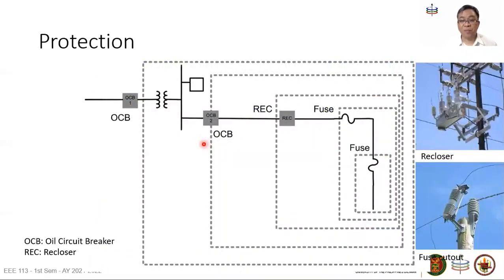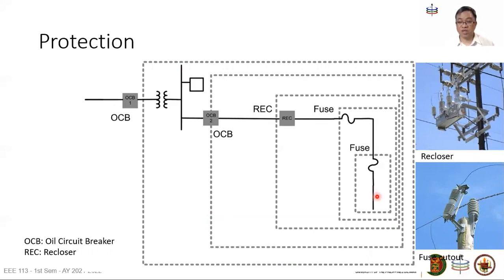To summarize system protection: the key principle is that protection devices must be in place and properly coordinated so that when a short circuit occurs, they minimize the effect and keep the trouble local, keeping the bigger system unaffected. This is simpler to illustrate in a radial distribution system where power flows unidirectionally, and becomes more complicated in a transmission system where power may flow from various directions.